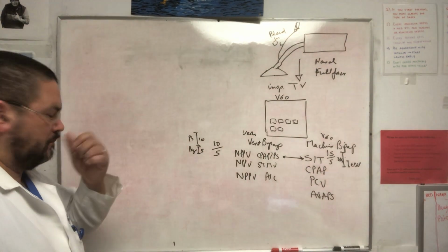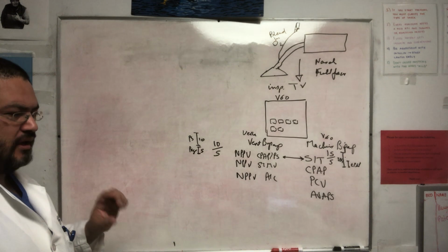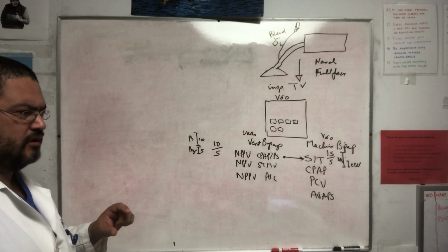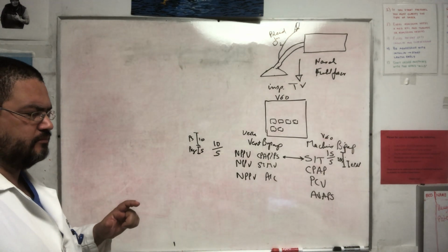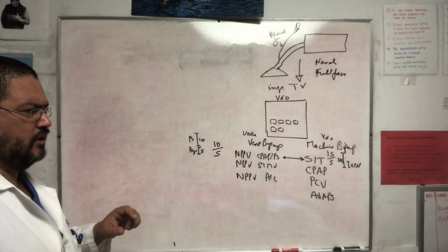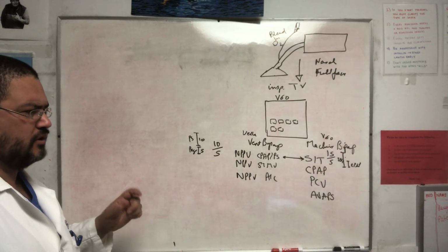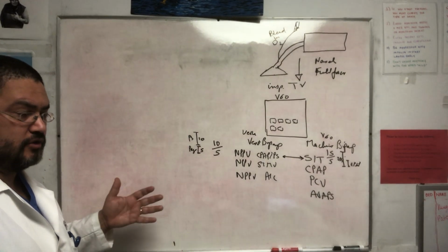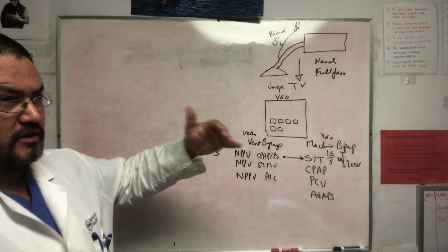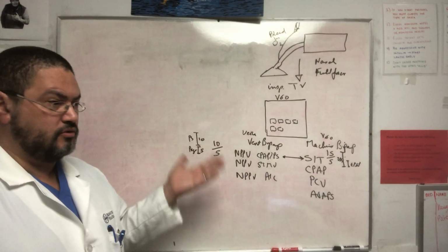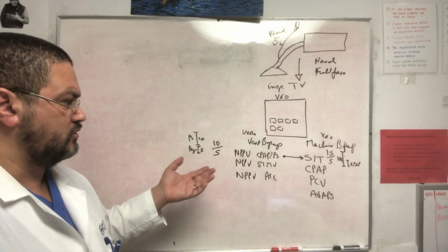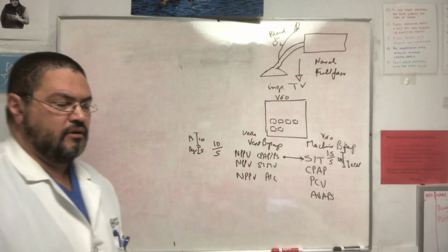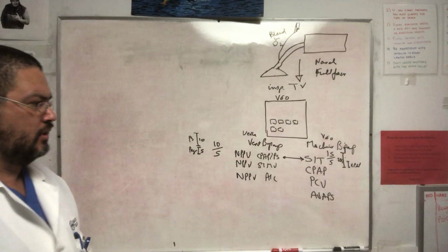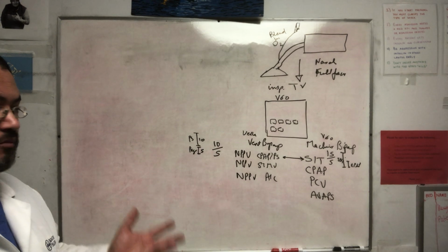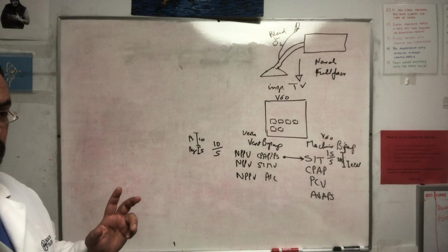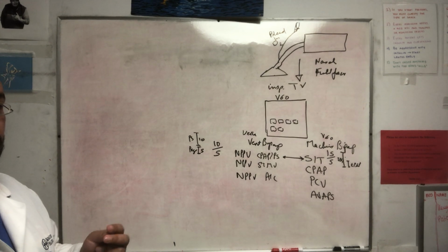So the EPAP is the end expiratory positive pressure, or expiratory positive airway pressure, and the IPAP is inspiratory positive airway pressure. So when it says inspiratory positive airway pressure, that means the maximum pressure during inspiration, right? It's not a pressure support, so that's why it encompasses the EPAP with it. Is this important? Looks like it's not that important, right? It is actually very important when people keep changing between BiPAP and vent. So you get confused what you're ordering, and sometimes they change without even telling you.